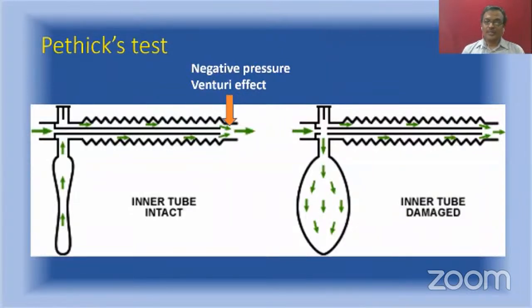Look at the picture on the left side. The inner tube is intact. You can see the Venturi effect caused the negative pressure, and because of the negative pressure here, the gas is sucked from the reservoir bag and the bag has collapsed. Look at the picture on the right side. There is an inner tube damage. See, there is a crack in the inner tube, and when you activated the flush, the fresh gas, instead of going through the inner tube, entered the reservoir bag and caused the inflation.